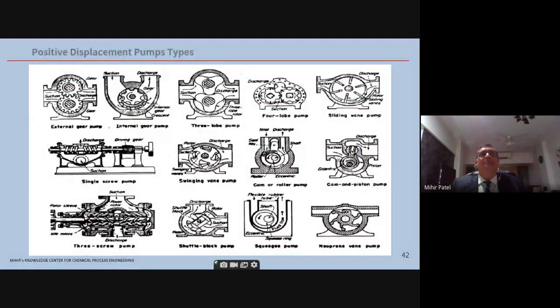Now we'll go to the PD pumps. There are many types of PD pumps, as can be seen, and each has a different application. For example, you see the single screw pump in the middle. This is specifically used for a large fuel oil network, where you have, let's say, 5-6 fired heaters and you are supplying fuel oil for burning to each. There's a large fuel oil tank, and then this single screw pump is there. I will be showing this in the utility section.